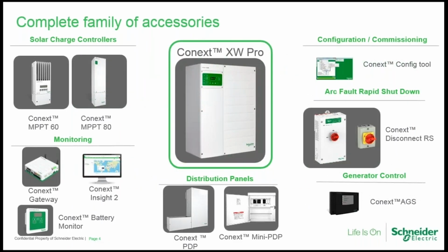So we're going to start out with an overview of our family of accessories, as well as our main topic is going to be centered around the XW Pro, battery selection and system sizing. I just wanted to quickly go through the accessories. Our 2 solar charge controllers: the MPPT 60, which is a 60 amp, 150 volt DC max on the PV side. We have an 80 amp controller, which is a high voltage charge controller. It's up to 600 volts DC on the PV side.